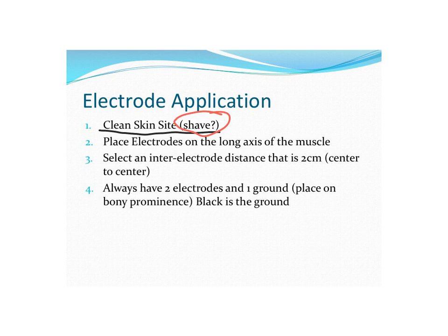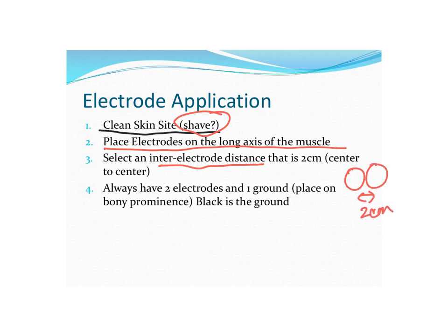You place the electrodes on the long axis of the muscle, and I'll show you an image of typical placements later on. Usually the inter-electrode distance is two centimeters, so place one and then the other within two centimeters. Always have two electrodes and one ground. The ground is usually placed on a bony prominence near the muscle belly so it doesn't impede movement, and typically in setups, black is the ground.